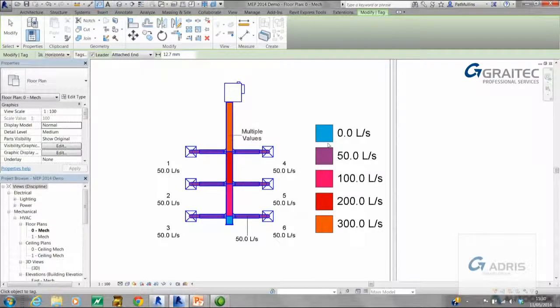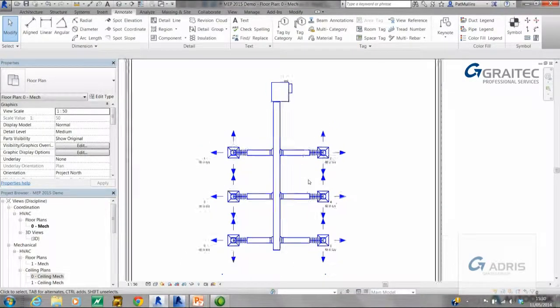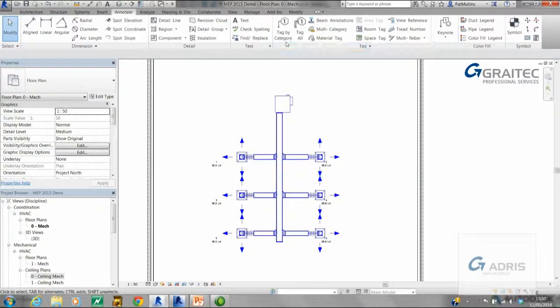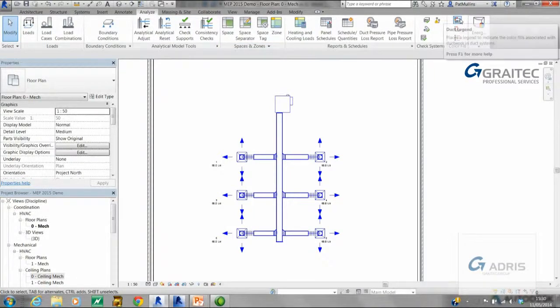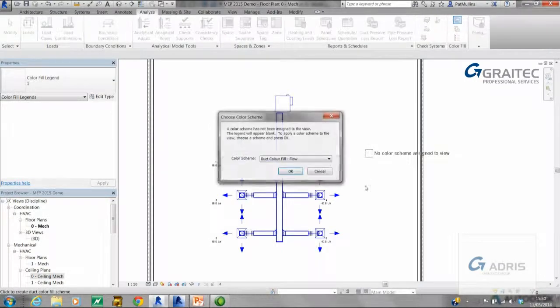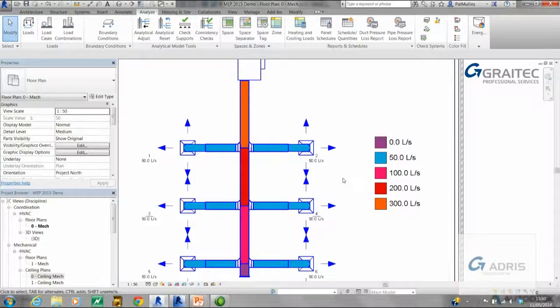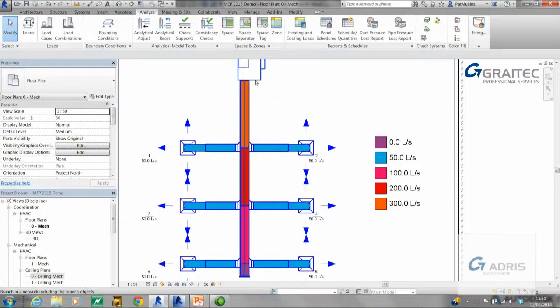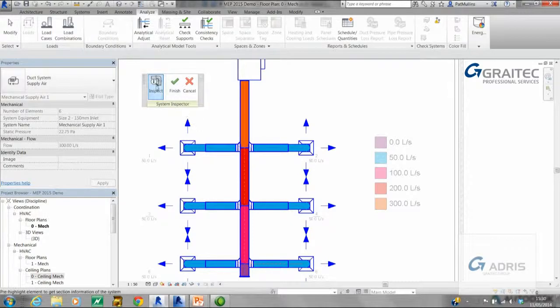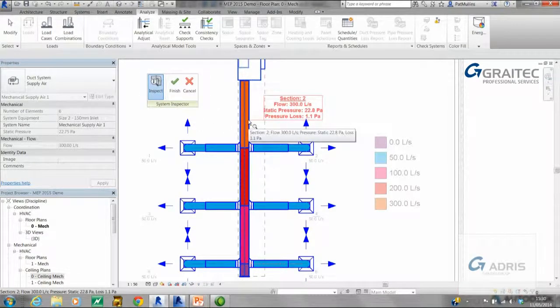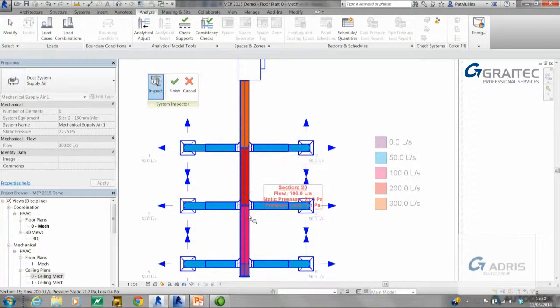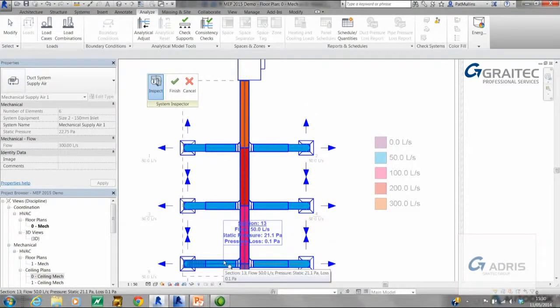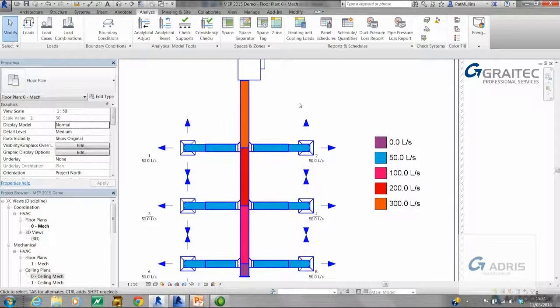So let's take a look at 2015. Here is another project, very similar. If I first of all place a duct legend down, it'll be associated with flow. As you can see here, the software knows about the flow assigned to each leg within the system. I can prove that by using the system inspector. As I hover over each segment: 300 litres per second, 200 litres, 100 litres, and that's made up of the constituent legs which are all 50 litres per second. So the software knows about the flow rate assigned to each segment.